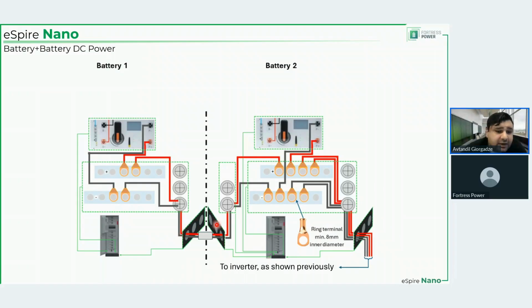You are introducing the conduit, and you are running this between the two batteries through the rubberized inlets, through the plates with conduit entrances, with the cables that you have supplied, because yes, we provide battery to inverter cables, but we don't provide battery to battery cables. So these cables will be procured and installed by the EPC or the installer. The same will be the case for this conduit right here. And you interconnect two batteries essentially in series, and then battery one connects to the inverter.